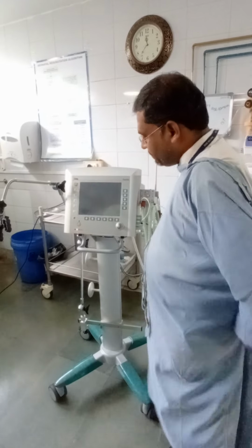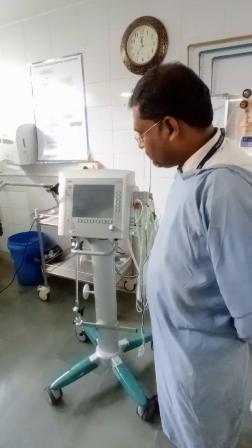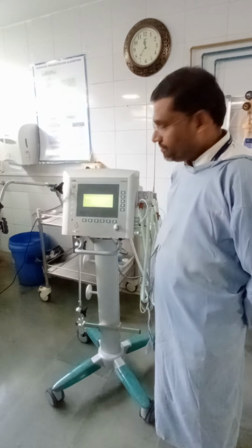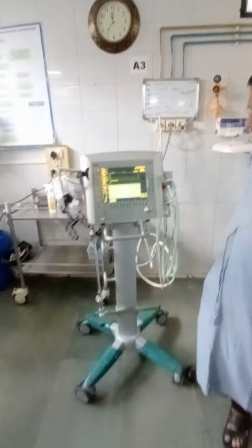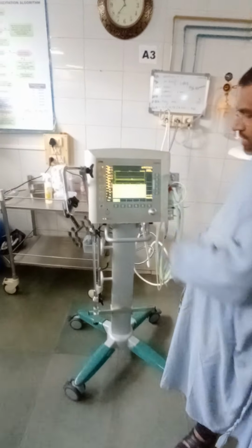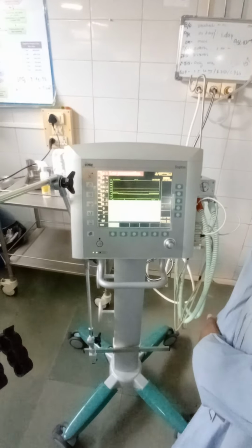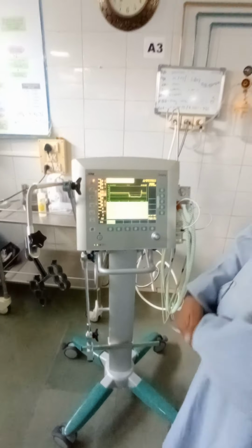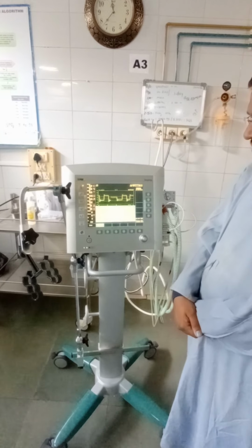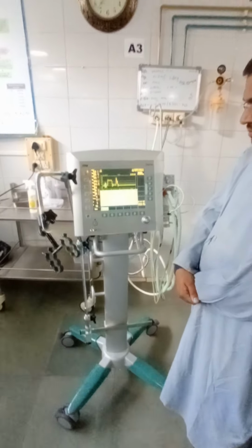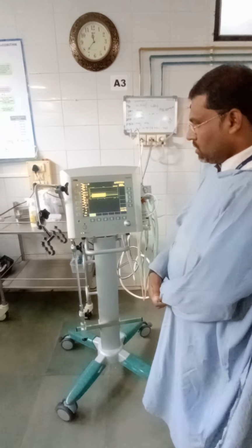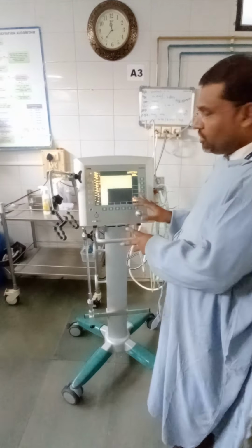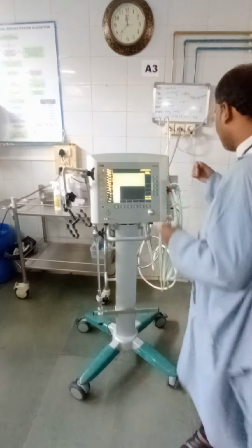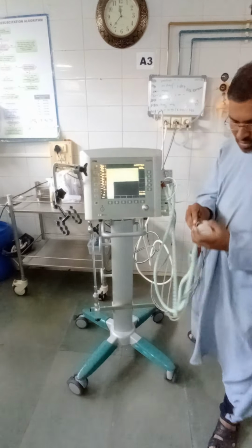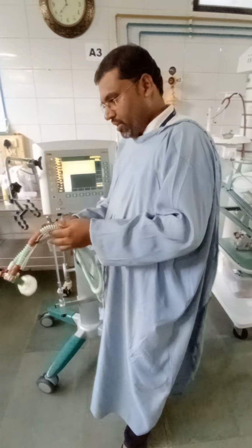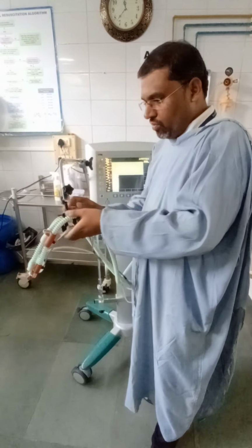Now machine gets started. System test is in progress. Please wait. Self calibration, and once your calibration gets finished, test mode finishes, select the ventilation mode, right? Now remove this end, connect the test lung, put it like this, and do whatever settings you require.